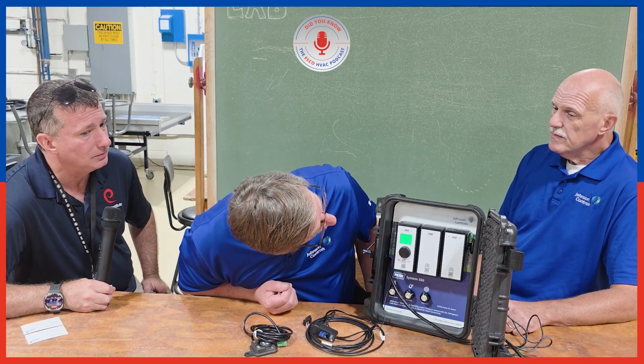From an energy standpoint, it's absolutely necessary. Yeah. If we think about, if we've got an ambient temperature that is 40 degrees, why do I go into defrost? I've already got some heat out there that I can utilize if I'm managing my defrost properly. That's correct. And then I can control the lengths of those cycles. There's a lot of flexibility in managing defrost, and we're going to handle a lot of capability then with the single modular control.